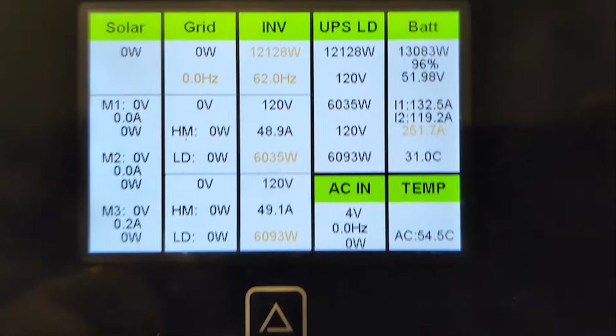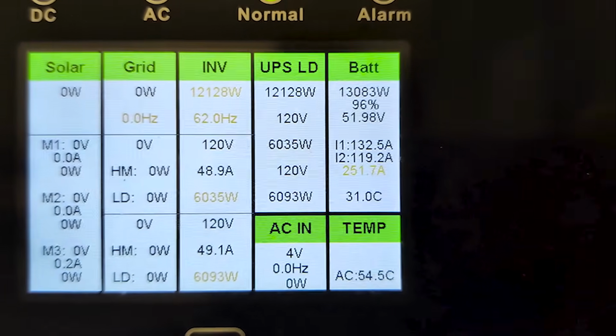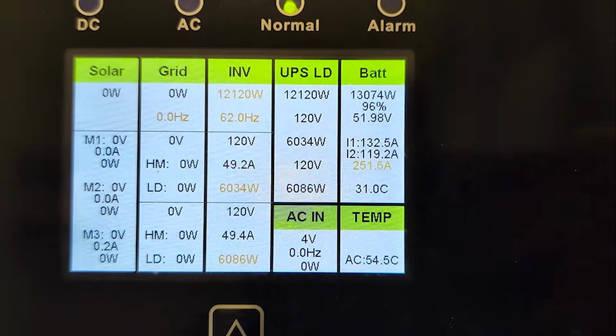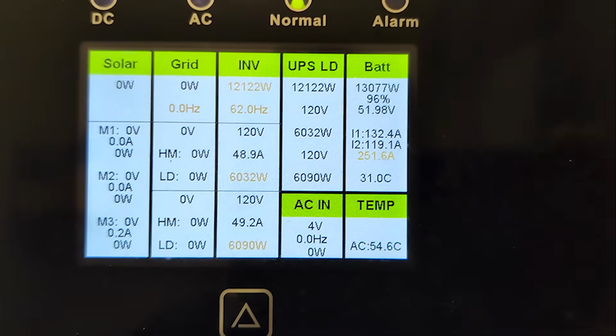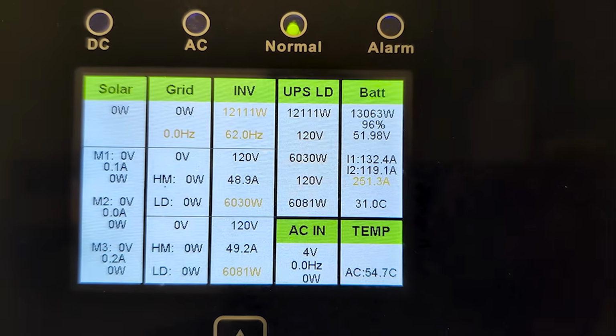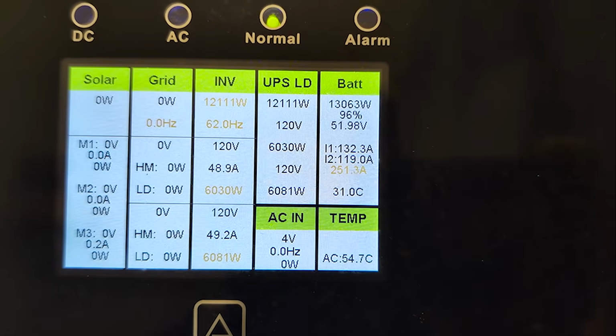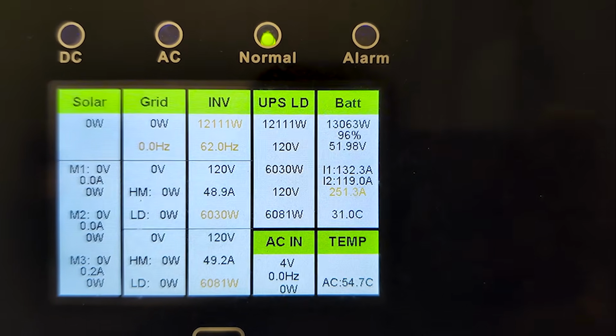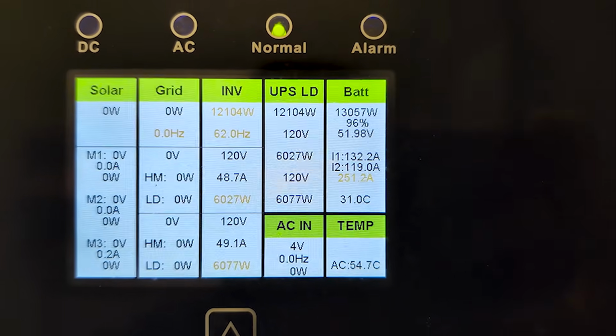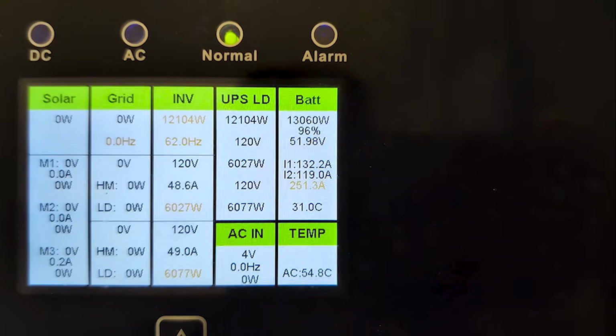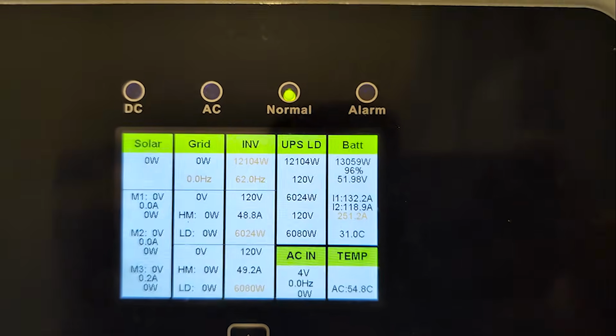We started at 52 degrees on our torture test, running without grid - no PV allowed, no grid, just battery to inverter. This is the worst condition you can run these in, but it's realistic. It can happen every day if you have an EV or any other constant load.